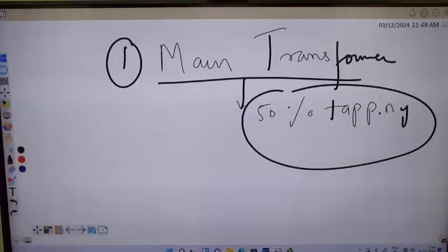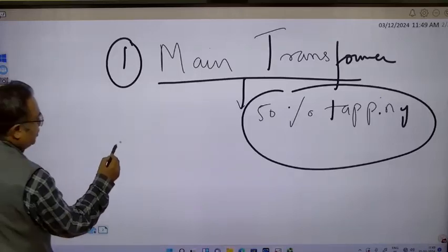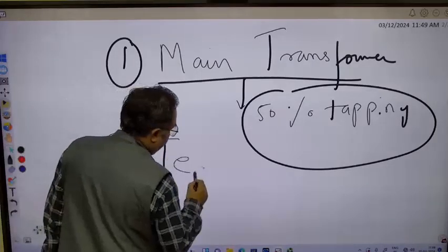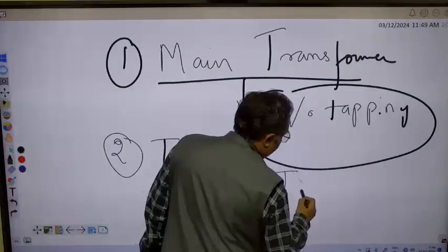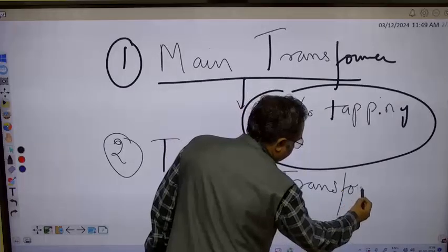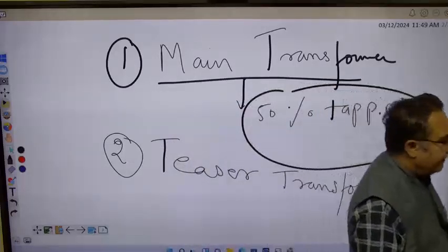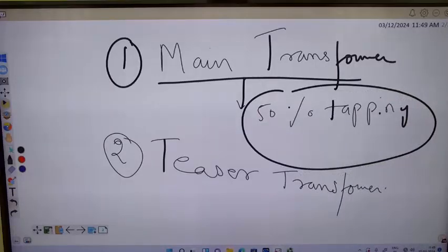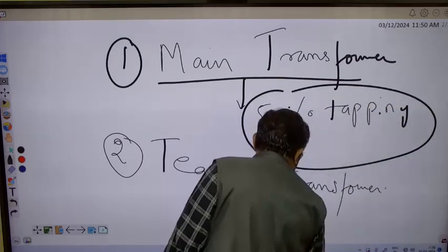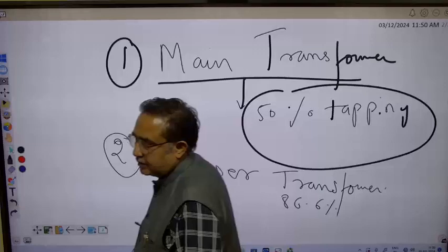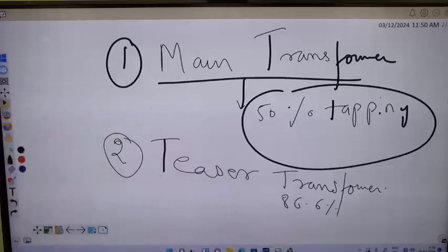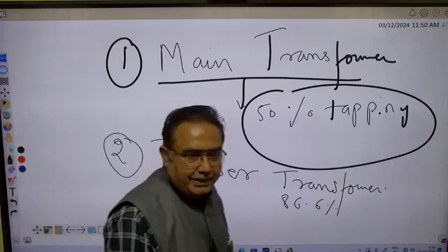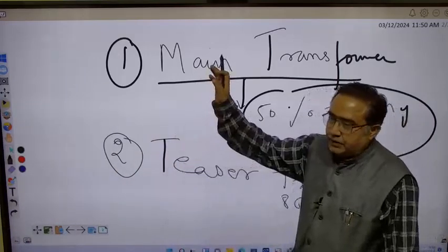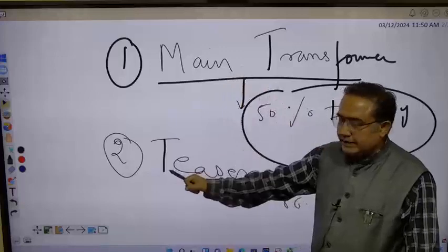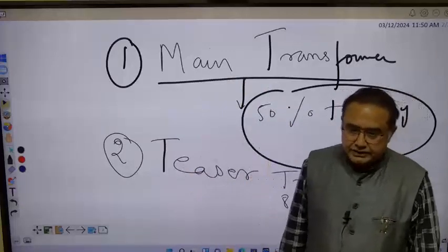First understand how connections are being made. The second transformer is called teaser transformer. And how much tapping is being used? 86.6%. So there are two transformers: one is main transformer having tapping of 50%, the other is teaser transformer having tapping of 86.6%.